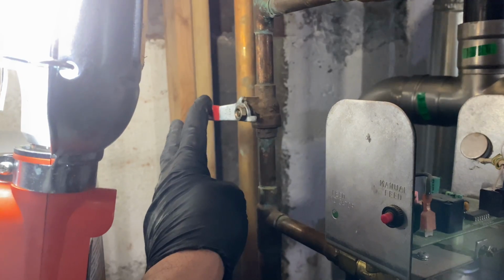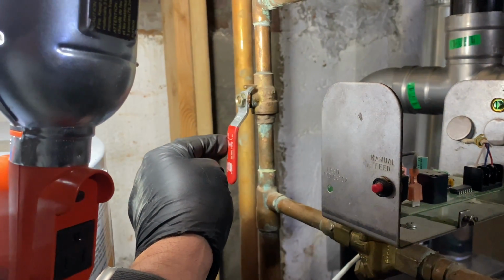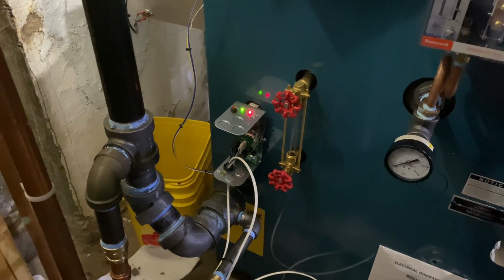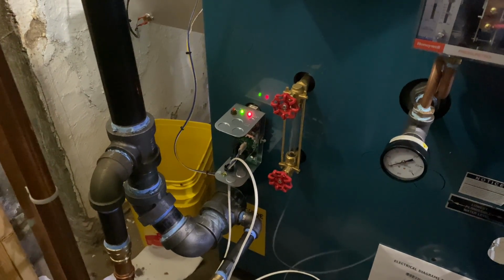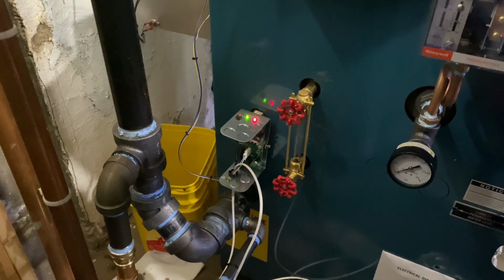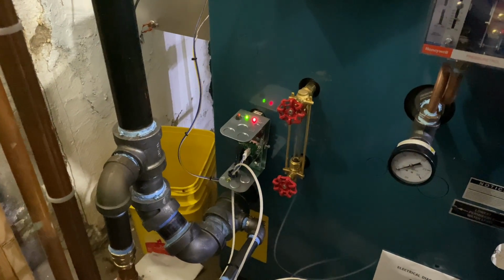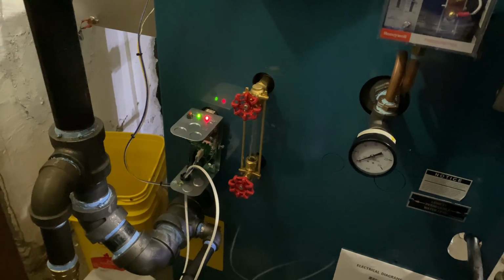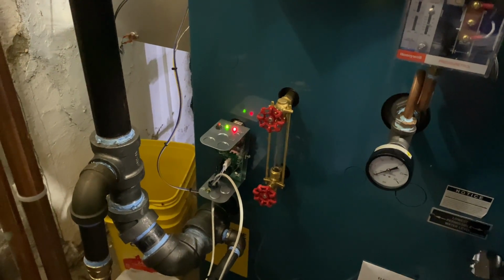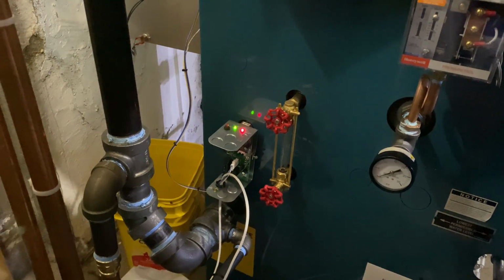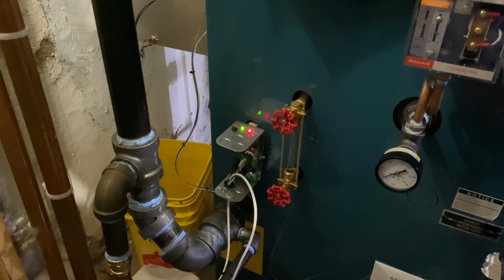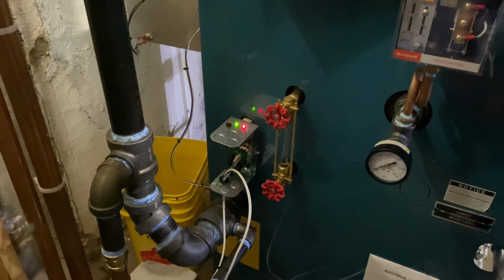Right? Yeah. All right, ladies and gentlemen, it's that moment we've all been waiting for. Filling the boiler. Power's on. We have a low water condition, or a low water indicator light on, or a low water cutoff, which is right there to the left of the sight glass. And once the probe senses water, that red light will go off. And as long as we have a call for heating, we'll have ignition.